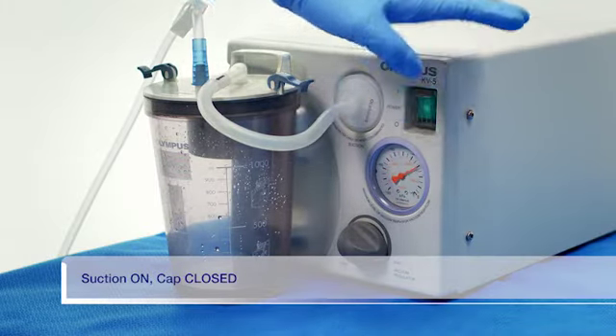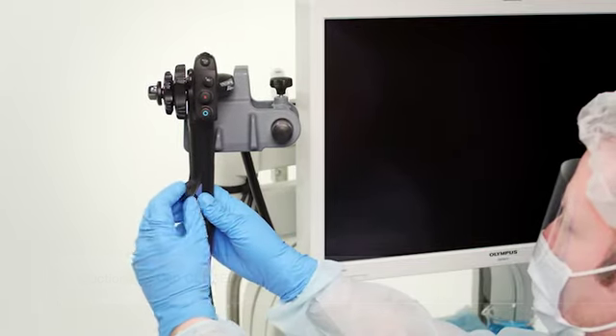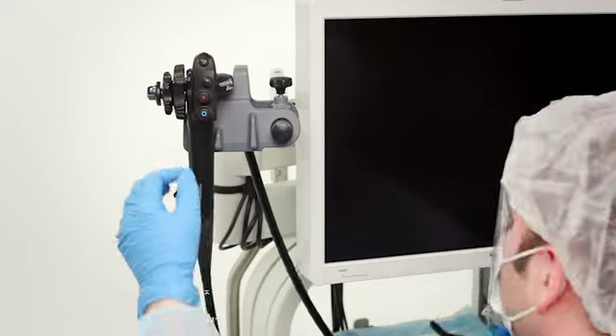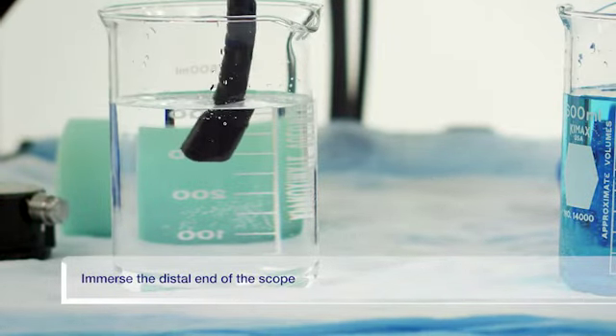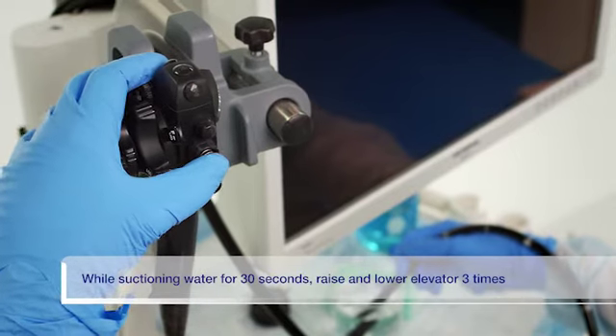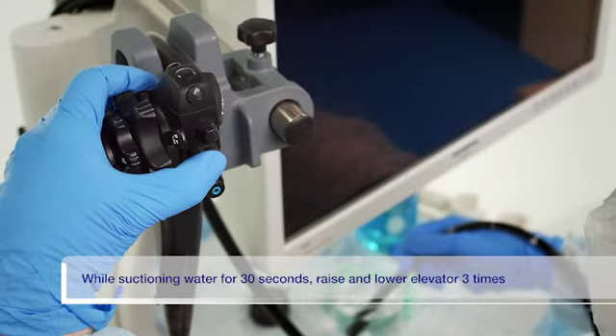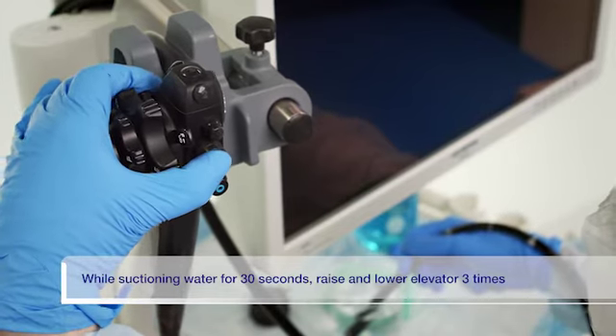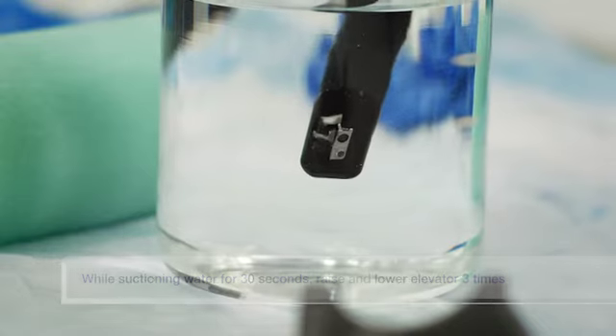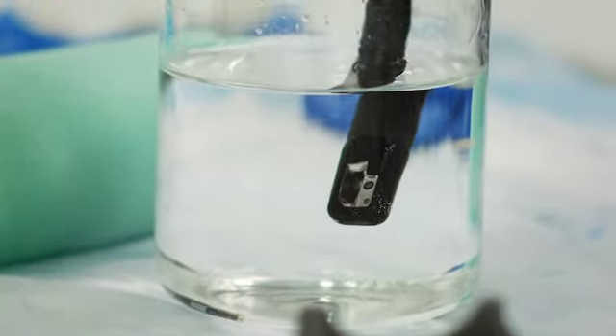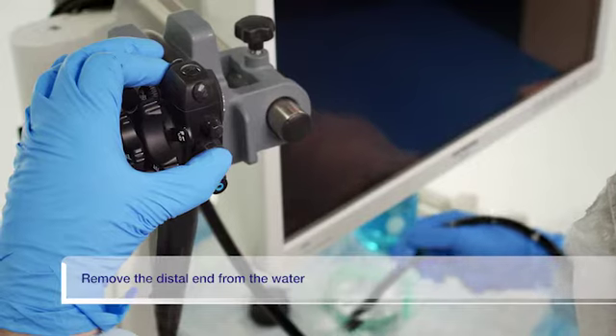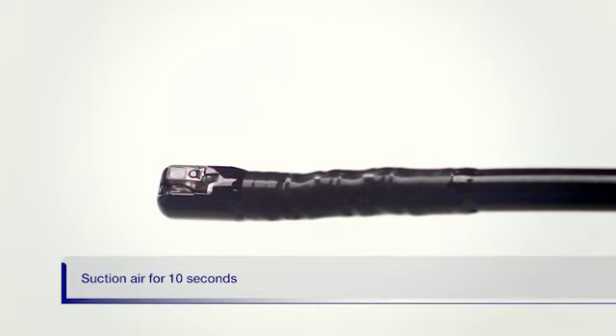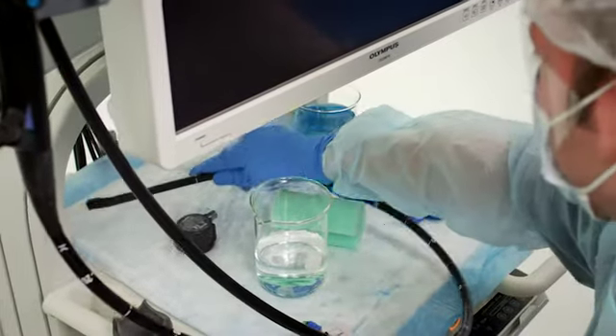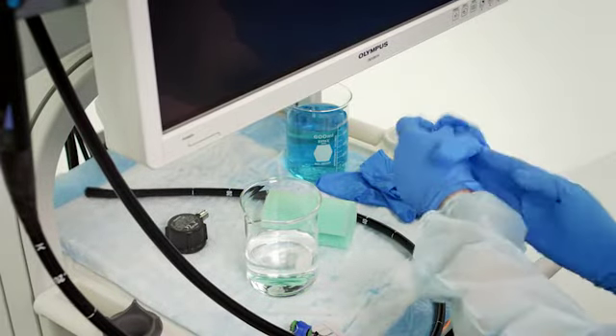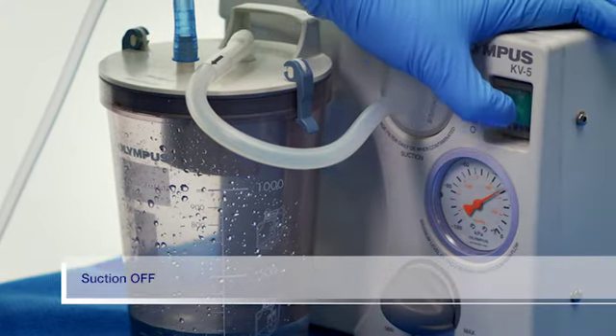Turn the suction pump on and close the biopsy valve cap. Lower the forceps elevator and immerse the distal end of the insertion section into the clean water. Depress the suction valve to suction water for 30 seconds. During this time, raise and lower the forceps elevator 3 times by turning the elevator control lever. Remove the distal end from the water and suction air for 10 seconds. Turn the suction pump off.